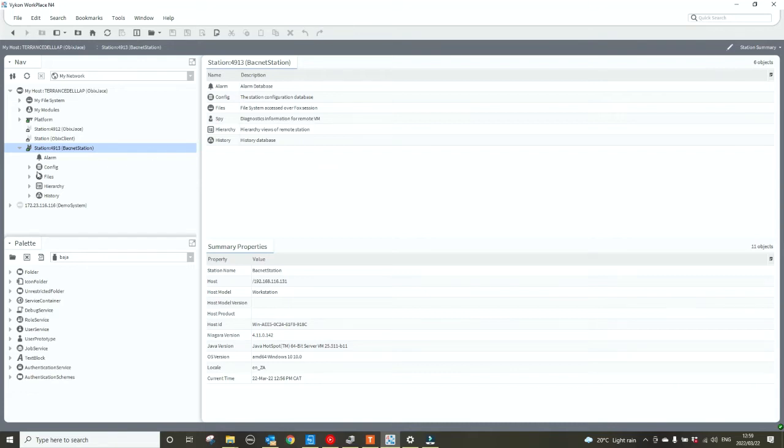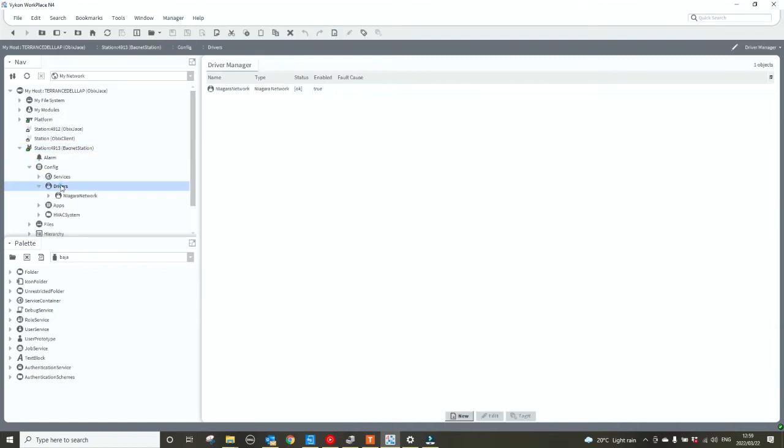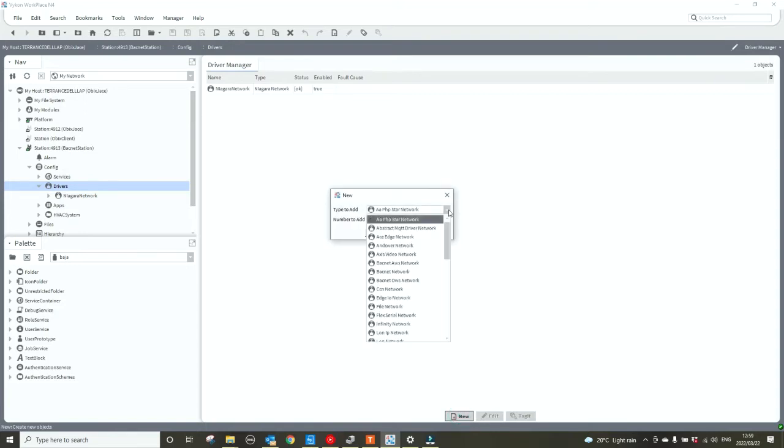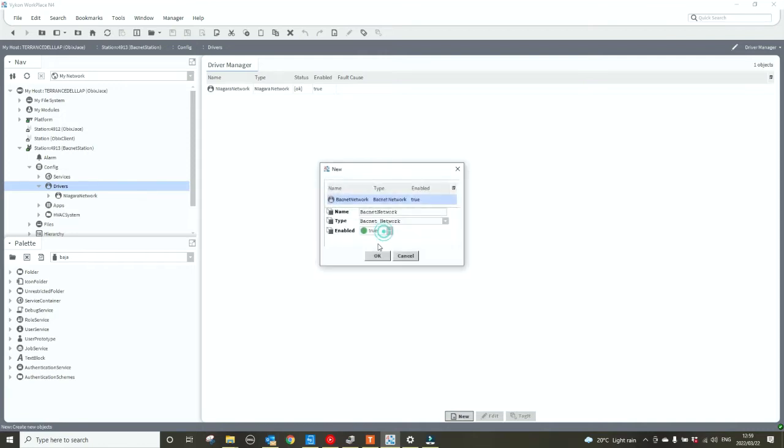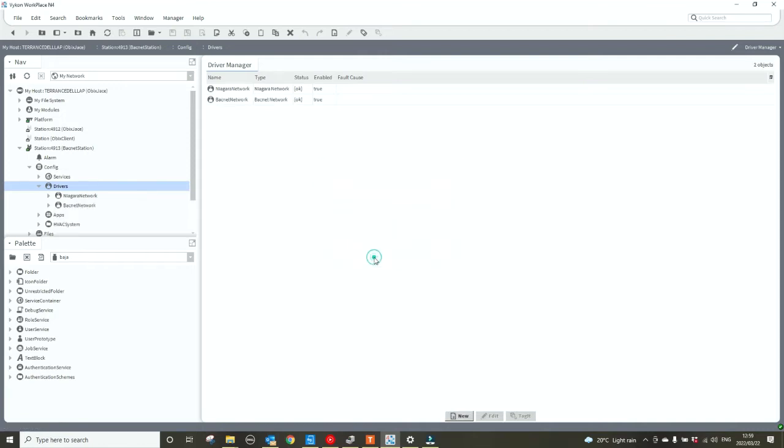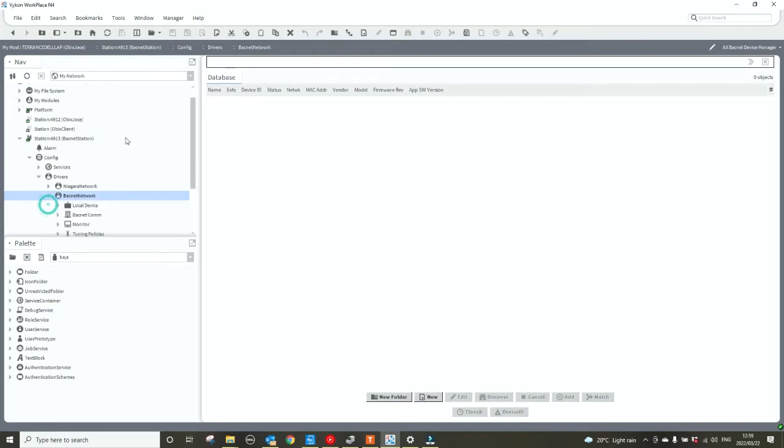We're going to go to the config space drivers, double click on drivers, click the new button. On the drop-down menu we're going to select the BACnet network, click OK and click OK. If I double click on the BACnet network, you'll see that the discover button is grayed out. We first need to configure the BACnet network so that we'll be able to discover devices.